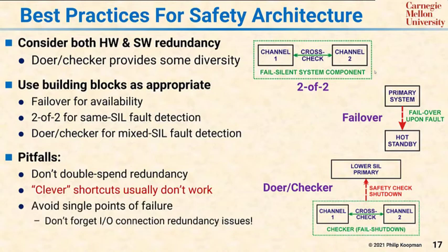Another aspect that's inherent in these diagrams is that you need to have sufficient I/O redundancy. If you have a single sensor or a single actuator, no amount of computational redundancy will help you if that sensor or actuator fails in a critical way.